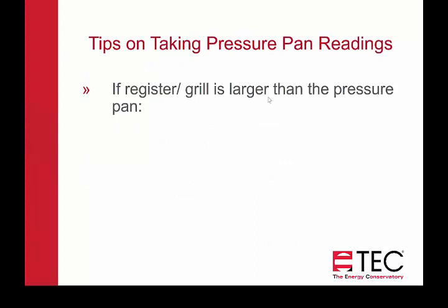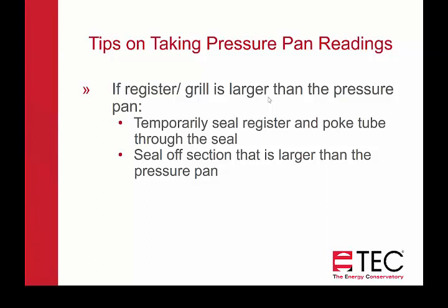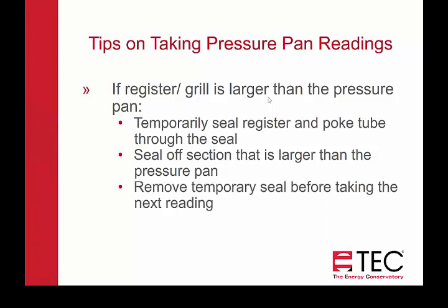If you run across a register grill that's larger than the pressure pan — for example, if you're using the smaller 12 by 14 pressure pan and you're measuring a central return grill — there are a couple of ways to handle that. You can temporarily seal that whole register and poke a tube through the seal, or you can seal off the section of it that's larger than the pressure pan and then use your pressure pan on it. Make sure to temporarily remove that seal before going on and taking your next reading, because that will affect your other readings.